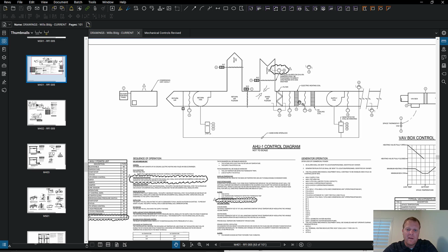So you might have to fake the demand. Might have to put this entire cooling coil going. You might have to figure out a way to create cold air coming back from the return side so that we could then tune that. Or you might just have to wait until there's colder air, and then there's a demand for it. And vice versa with the cooling coil, right? If the air is already cold, how are you going to make a load for this condensing refrigerant cooling coil here? Well, that would be more simple because you could actually heat up the coil right before it with the boiler, and then you could immediately cool it off right here with this one to test it.